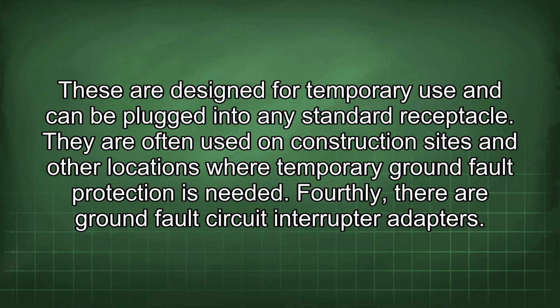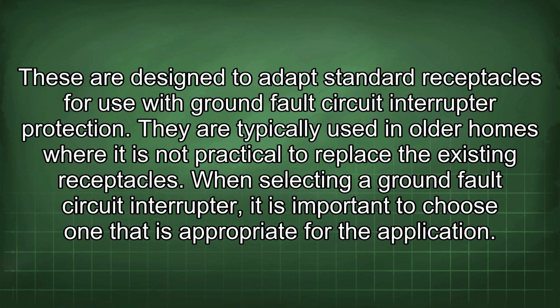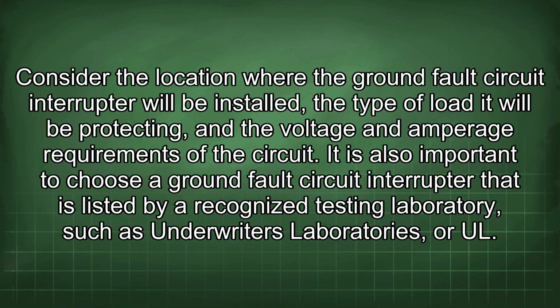Fourthly, there are ground fault circuit interrupter adapters. These are designed to adapt standard receptacles for use with ground fault circuit interrupter protection. They are typically used in older homes where it is not practical to replace the existing receptacles. When selecting a ground fault circuit interrupter, it is important to choose one that is appropriate for the application. Consider the location where the ground fault circuit interrupter will be installed, the type of load it will be protecting, and the voltage and amperage requirements of the circuit.